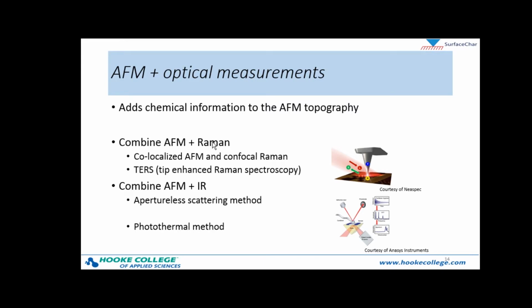AFM and Raman, the most popular way that's being done right now, is doing what are termed co-localized measurements of AFM and confocal Raman on the same area. And then for higher resolution, there's a technique called tip-enhanced Raman spectroscopy that's available. In order to combine AFM and infrared spectroscopy, there are also two main methods out there. One is an apertureless scattering method, a schematic of which is shown here, where you use the AFM tip as a very sharp antenna to really focus the IR light right underneath the probe. And then another method is a photothermal method that relies on some mechanical motion of the lever in response to some heating by the IR laser.